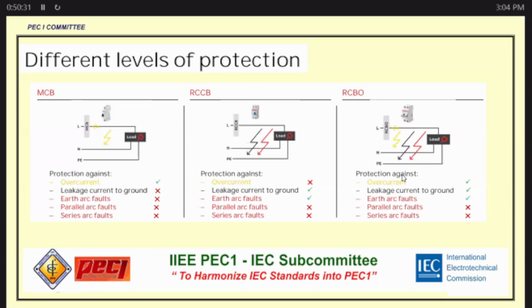Number two, how about your residual circuit breaker? The residual circuit breaker can only protect against the leakage current to ground, or the residual, and then the earth arc fault. Because residual and earth arc fault are basically the same. That's why the residual circuit breaker, or what we call GFCI in ANSI terms, we need, guys, to be familiar with the IEC term too.